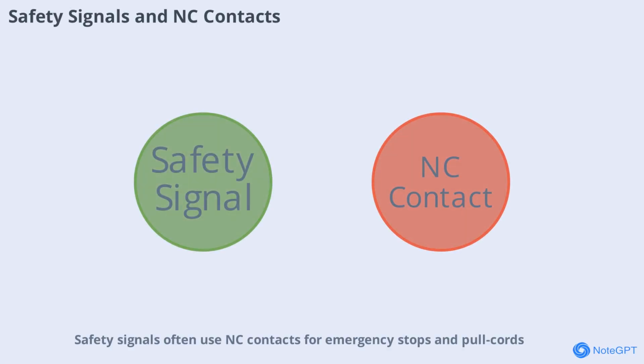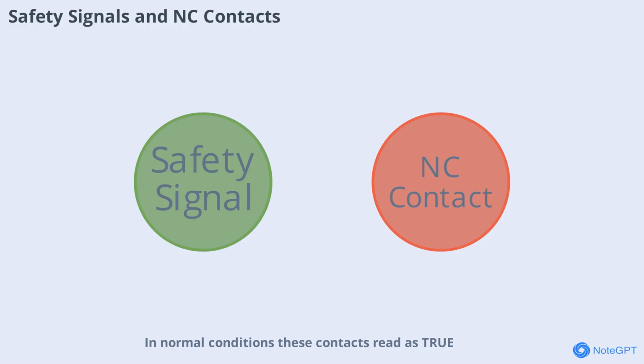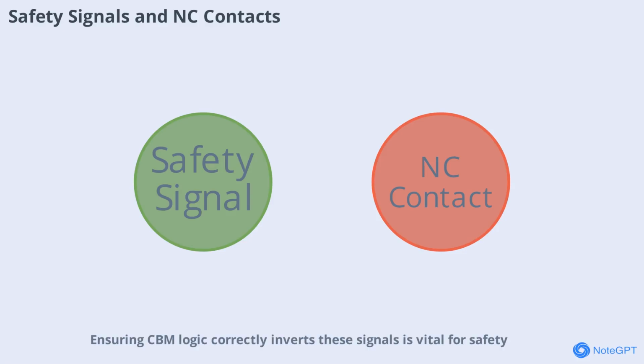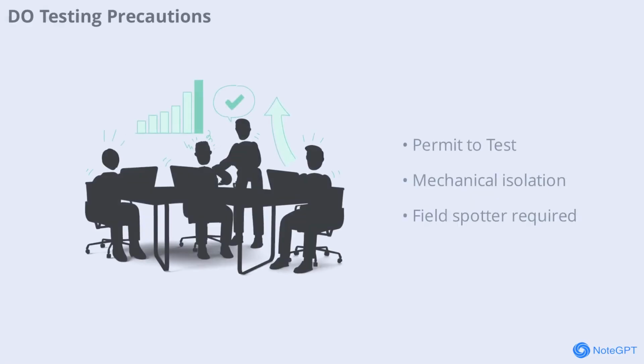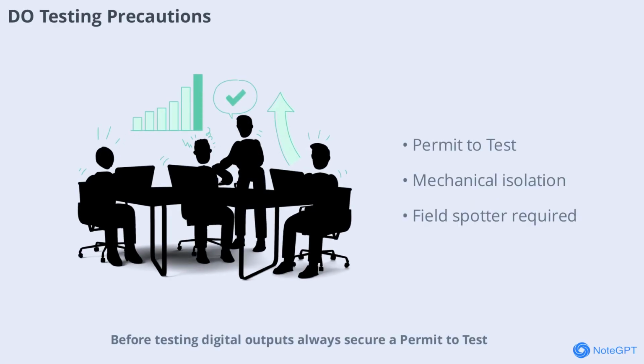Safety signals often use NC contacts for emergency stops and pull cords. In normal conditions, these contacts read as true. If the wire breaks or the sensor trips, the input drops to false, signaling a safe fault state. Ensuring CBM logic correctly inverts these signals is vital for safety. Before testing digital outputs, always secure a permit to test, ensure mechanical isolation, and have a field spotter verify that the equipment is clear.